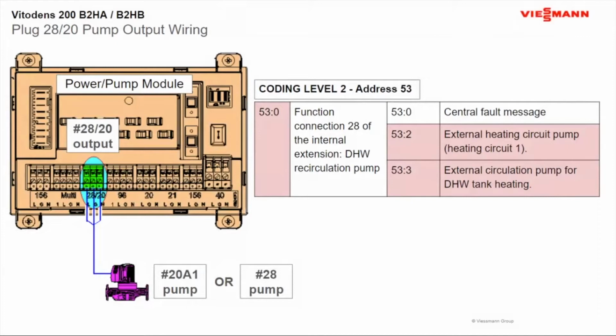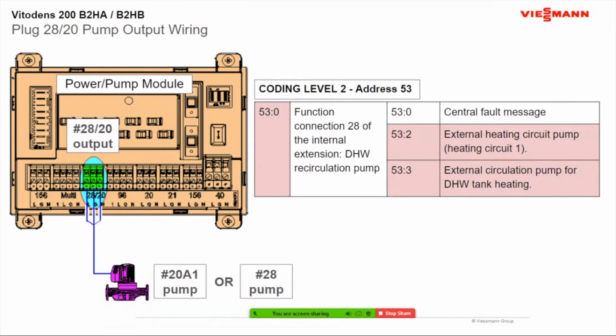Just showing your pump output. So when we go through this, you'll see it'll make more sense when we go through the startup wizard. It'll ask you to pick a pump output like your 2820 or your 157 pump output. When you're done, it will give you a summary of what pumps you picked and where you're going to wire them to, but you can actually go into your coding and change it as well. Say you don't want it to be a recirculation pump, you want it to be a heating pump. You can go in there and change it just by going into coding.